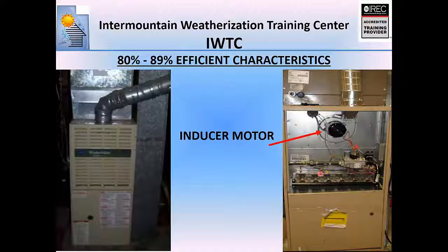And there's little protection devices right here, like this, if you can see it. That's called a rollout switch. There's another one right here. Should this start to backdraft, it causes the flames to roll out. Hopefully the rollout switches shut everything off before it burns up all the wiring or starts a fire.